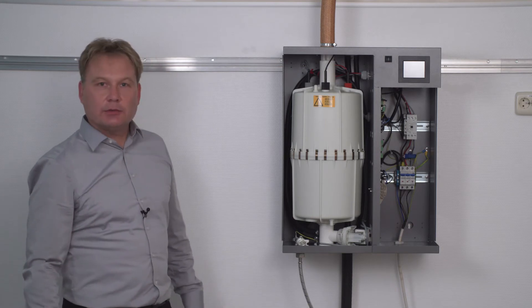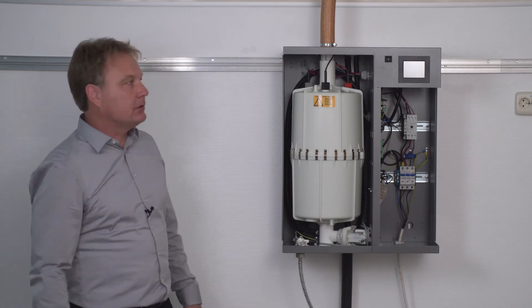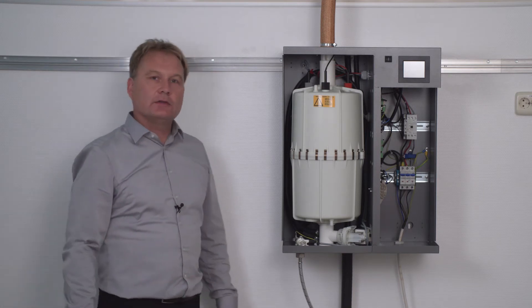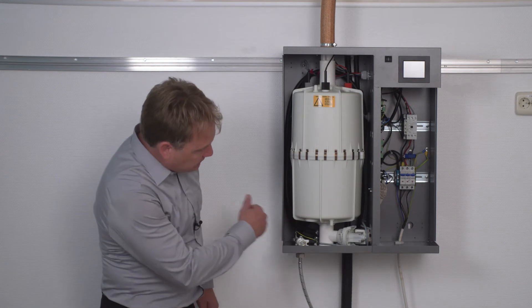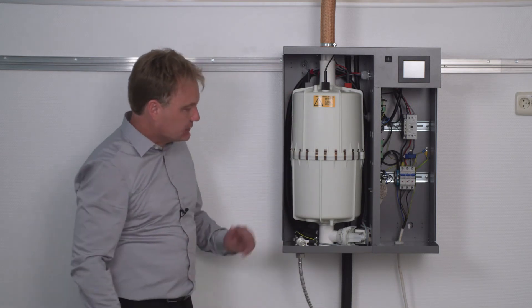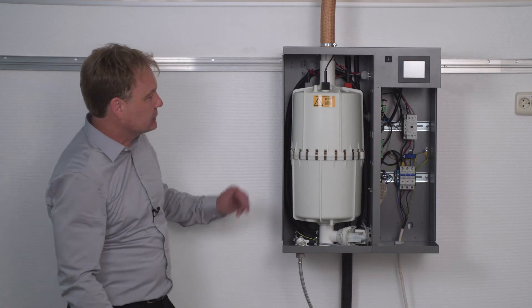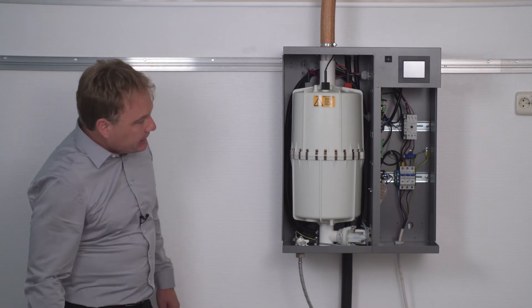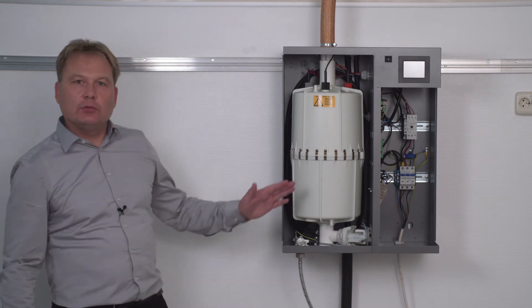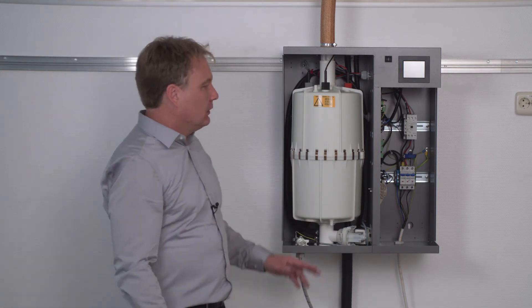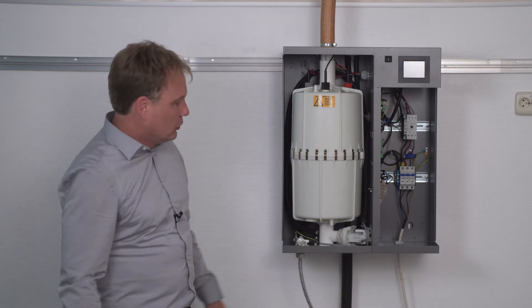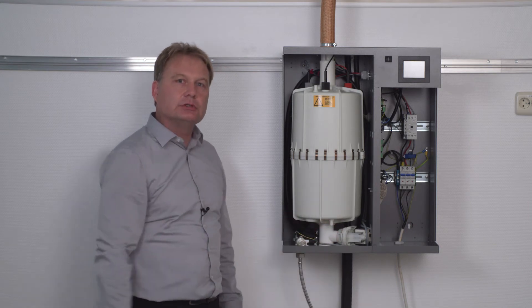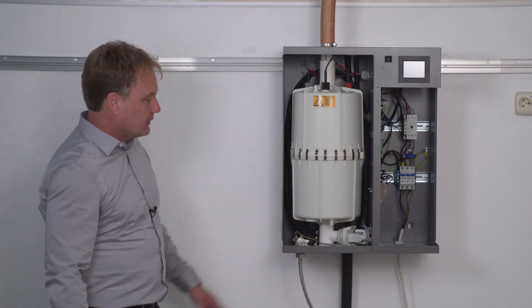After the steam cylinder has been installed, start the test run. Simply let the device run for 10 minutes. And during the test, check all areas with replaced O-rings for leaks. Check for leakage, especially here around the cylinder flange. After having done this, after about 10 minutes, please pump out the water too, to see if there is any leakage in the area of the blow-down pump. So it must, of course, be taken care of immediately.